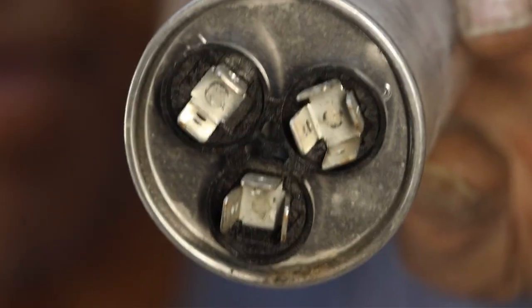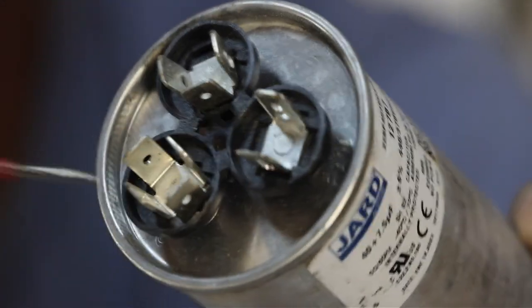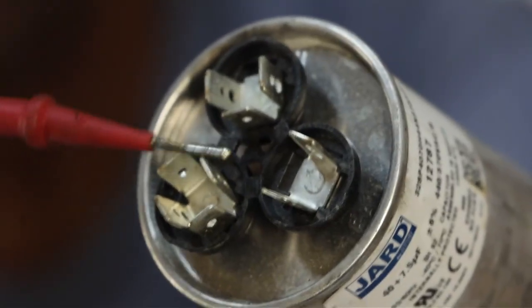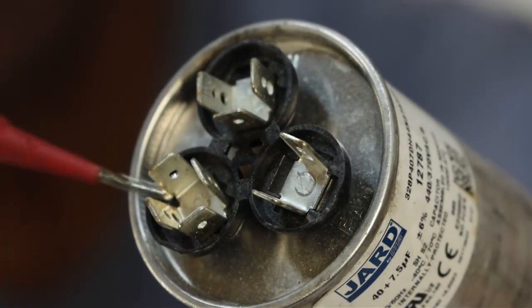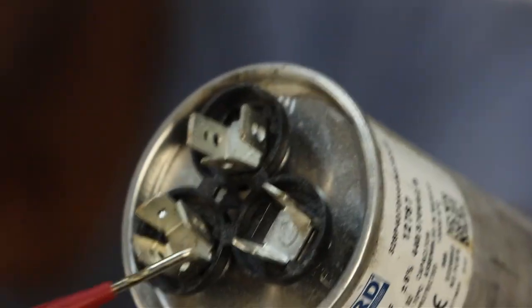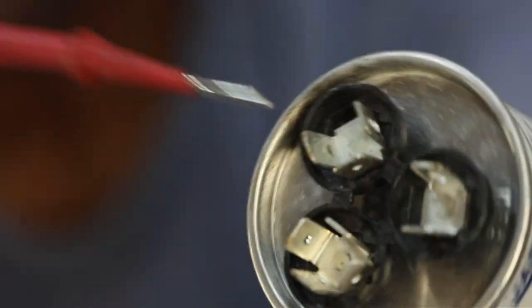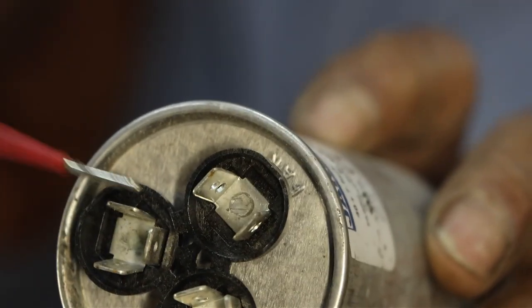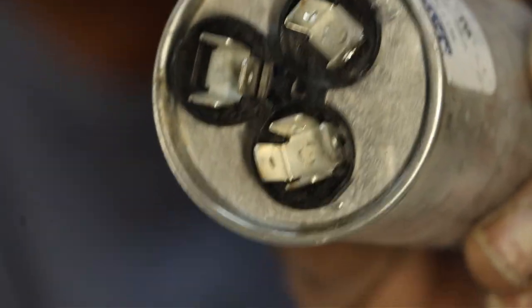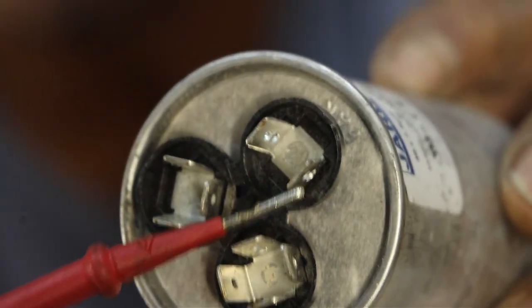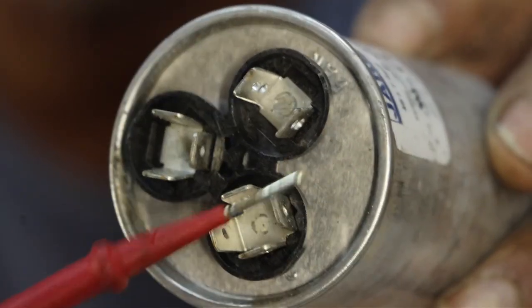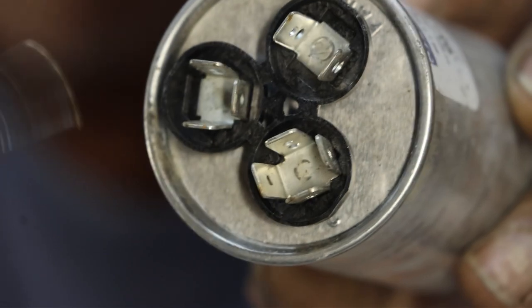And that's talking about the fan motor. Now, one of the ways you can identify the common is it will have 4 prongs. If you look, the common has 4 prongs on it. So 4 different things can connect to that common. But the hermetic only has 3. That's up at the top here. The hermetic for the compressor only has 3 prongs. But then on the fan, I'm not looking at it, but experience tells me there should only be 2 prongs on where it says fan. That's how you can identify what connects to what on your dual outdoor capacitor.